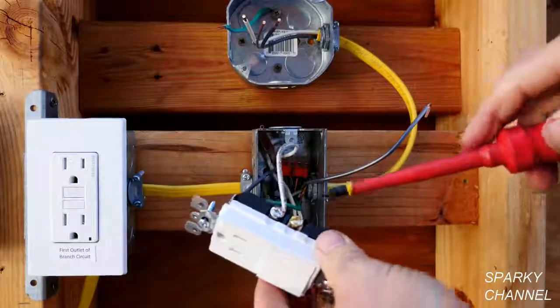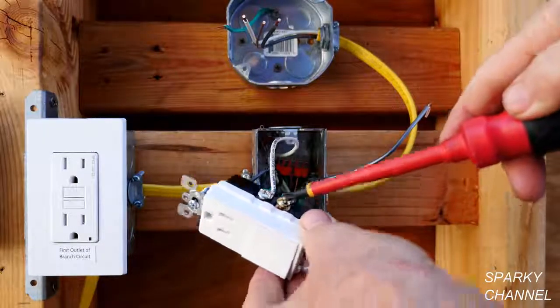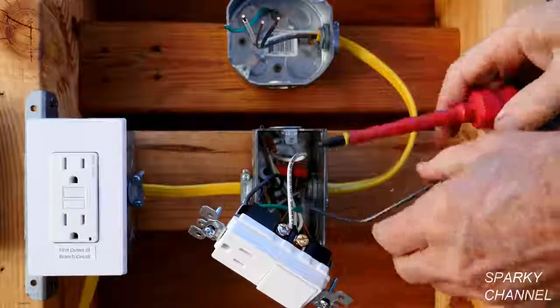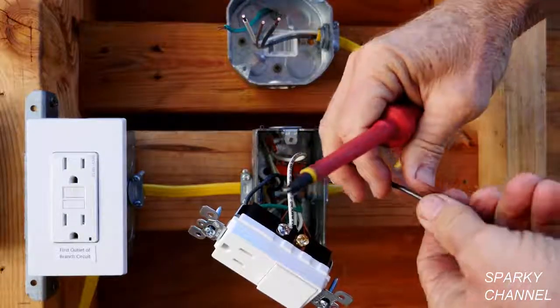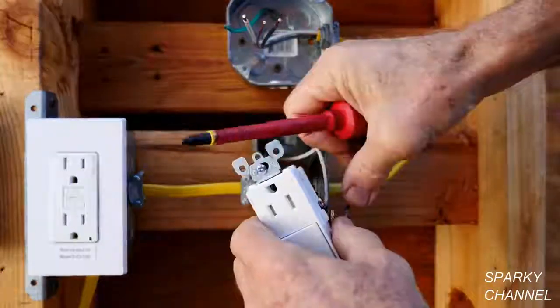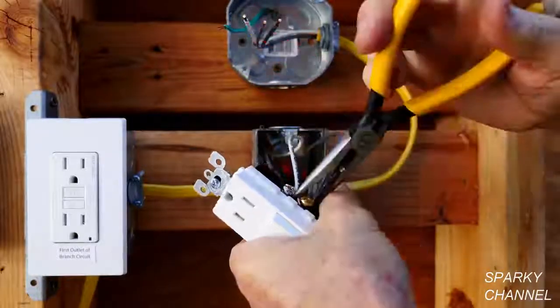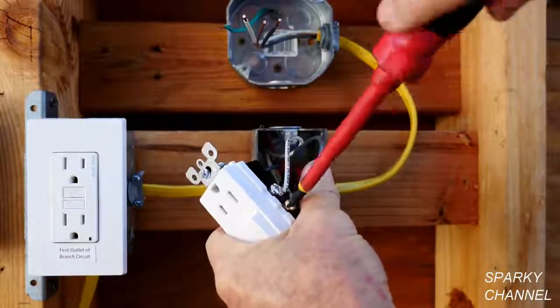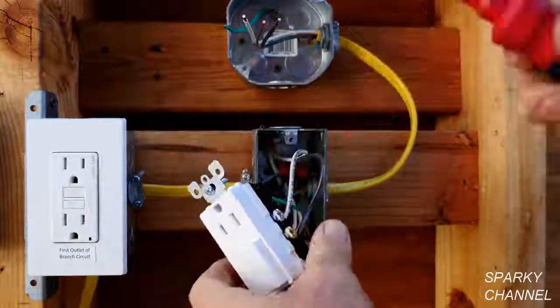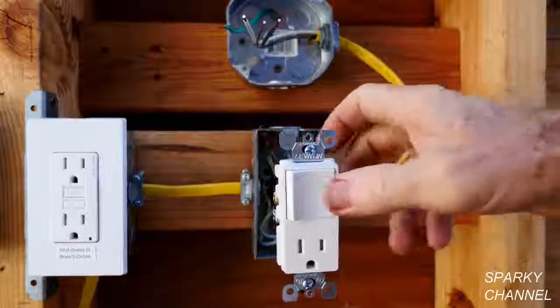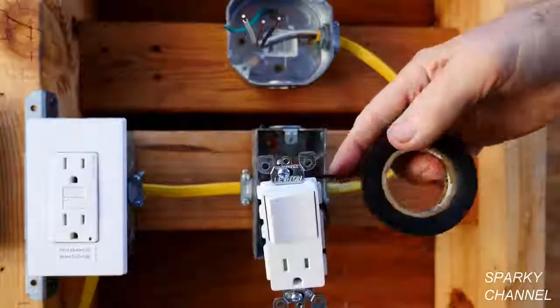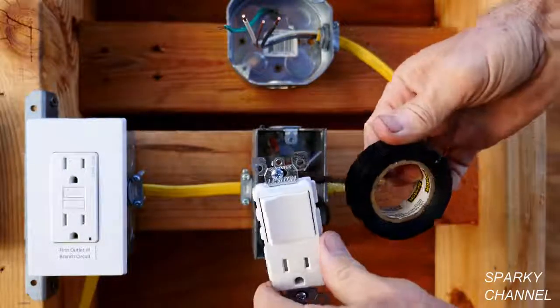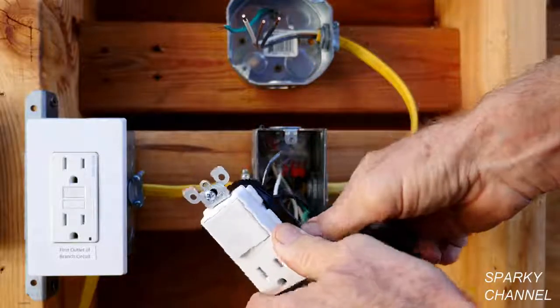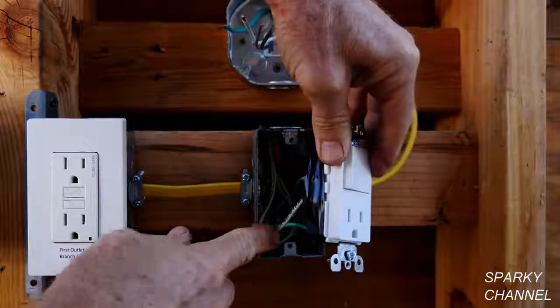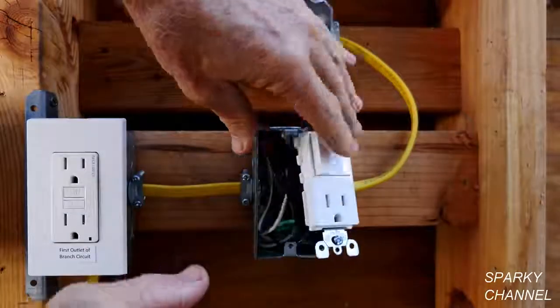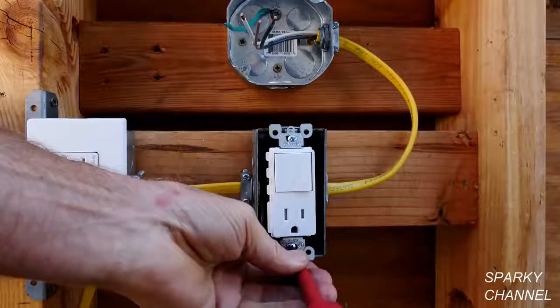So here is where the load wire goes for the switch. And this is our load wire that goes to the light. So we put it around the terminal in a clockwise manner. Tighten it down securely. I like to put the switch on top and the receptacle on the bottom. Now I'll put a couple wraps of black electrician's tape around the device for safety. Now you dress the wires. That is, you give them all their appropriate bends so that they push in kind of like an accordion, and tighten it up.